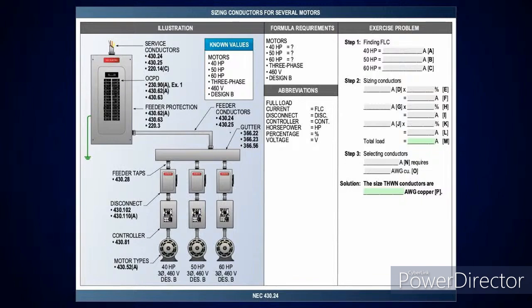And like in here, we show 3 motors. You've got a 40, 50, and 60. All you have to do is get the largest motor, which is going to be the 60 horsepower, take it at 125%, add all the rest at 100%, get your total amperage, go to table 310.16, 75-degree C column, and find the conductor that's above it. It's that simple.